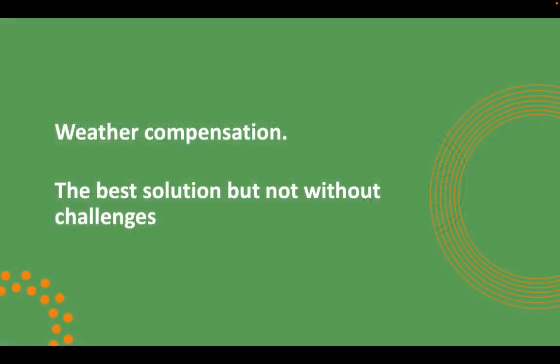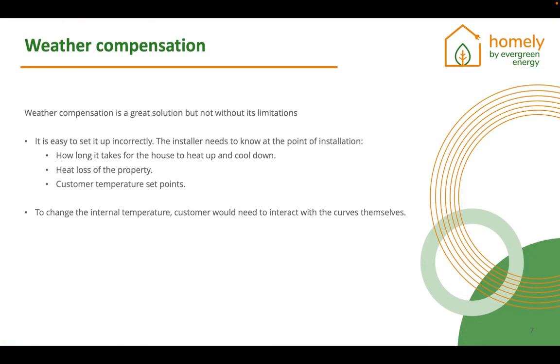Weather compensation, we think, is a great solution, but it does have its challenges. At the point of the installation, the information about the property might not be known in advance. So even though we do the heat loss calculations for the house, it might be that those calculations are slightly off. And if we were to set up weather compensation data just using that information that we've collected doing a visual inspection, it might be that the calculation is incorrect.